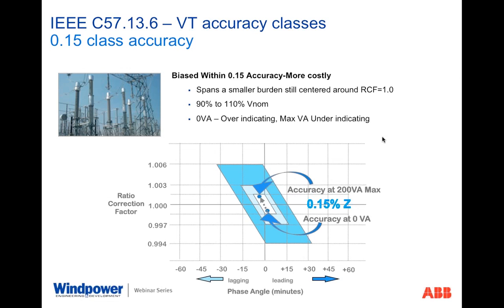But yes, we do have a 0.15 accuracy class, and we do have some customers who purchase the 0.15 accuracy, but keep in mind, the intent here, of course, is to be equitable. So a 0.15 device is more equitable than a 0.3, and it's more accurate, and it meters power more accurately. But let's look at it from the perspective that tightening that device into the 0.15 parallelogram, I'm actually biasing it with less overbilling on the low VA connections, i.e. solid-state metering connections. It's less overbilling, still within the accuracy class, and is still 0.15, which is better than 0.3. But you have to be concerned about paying more to have less over indication on your metering point.